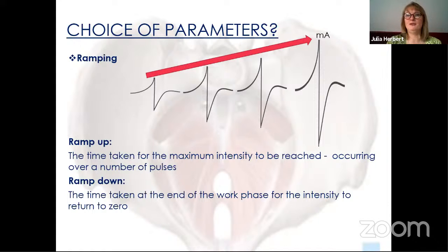So you need to be careful, because if you set a ramp of 2 seconds to get up to your maximum intensity, but your work was only for 3, then effectively you're only working at your target intensity for 1 of those work seconds. I think in the TensCare units, when I was looking at the data, it's actually an addition at the beginning, but we can perhaps take that in the question section, and some of your technical guys, if they're around, can explain how it works with your TensCare equipment.